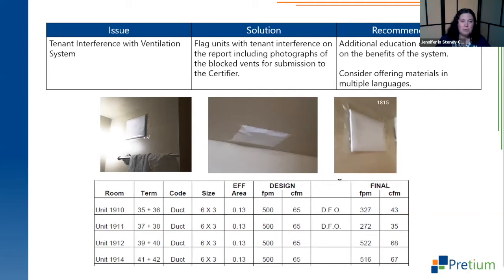So obviously what happens when we try to balance the system is we're finding units with a significant variation from the design CFM to the final actual measured CFM. We made a lot of effort and worked really hard with the client and the representation on site. We had the contractors enter these units, remove all of the coverings off of the vents, and speak with the owners or tenants one-on-one to say, this is why we're doing this. Despite that, many of them advised, as the contractor was walking out the door, that as soon as you leave, I'm putting it back.